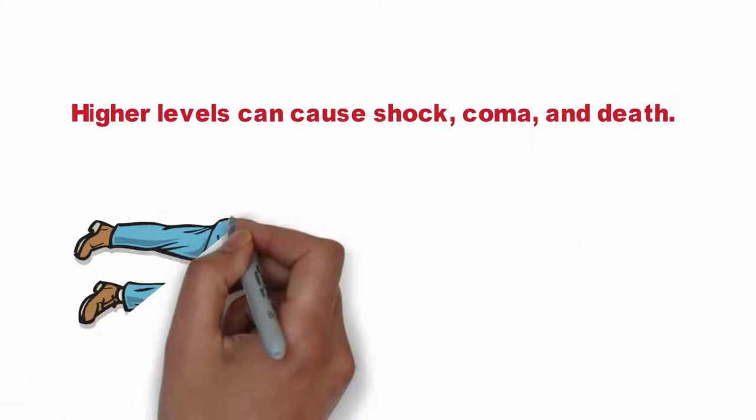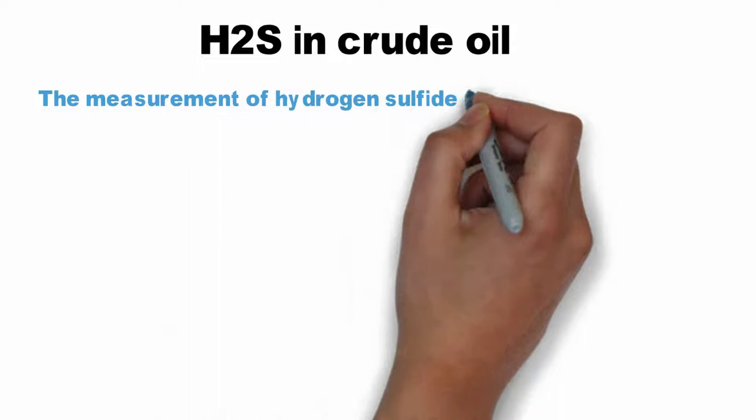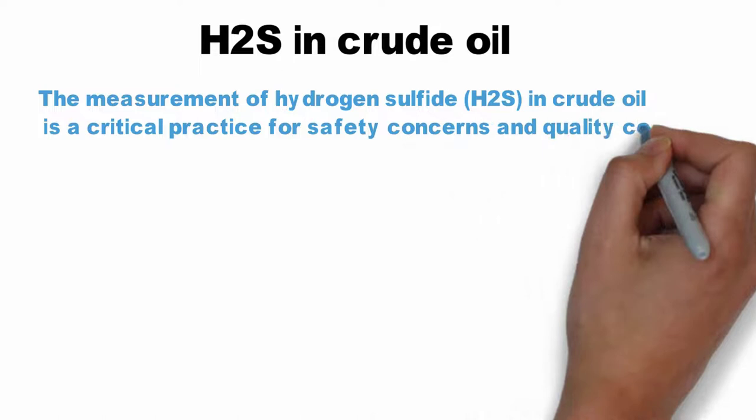The measurement of hydrogen sulfide H2S in crude oil is a critical practice for safety concerns and quality control. Hydrogen sulfide H2S is heavier than air and will settle into low areas.